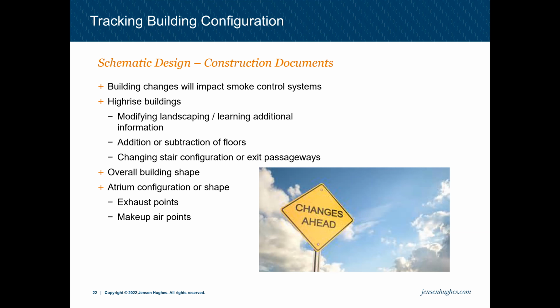Similarly, if you're adding or subtracting floors or turning a penthouse into an occupied story, that can impact the smoke control system also. Then lastly, for stair pressurization systems, if they use an exit passageway or some other kind of configuration on the first floor to get to the exterior, if that gets changed during the building design, that can also impact your smoke control system. Moving through there, the overall building shape can impact the smoke control system. And then the atrium configuration or shape also.